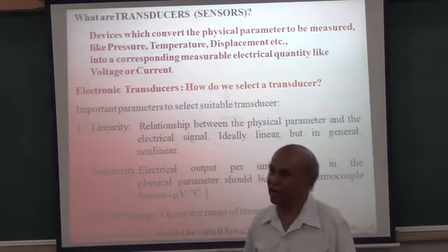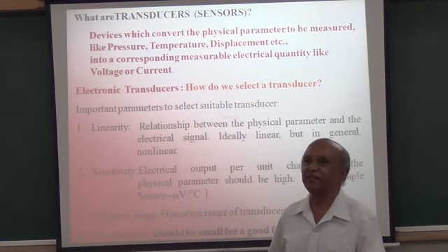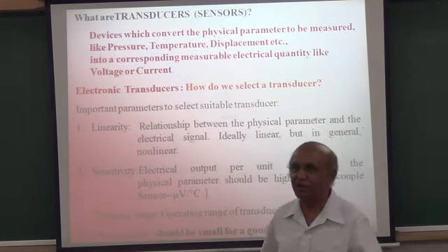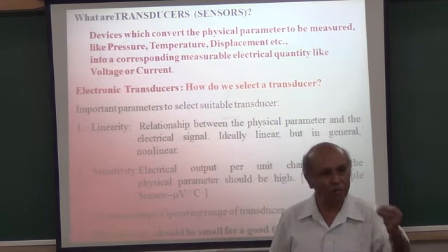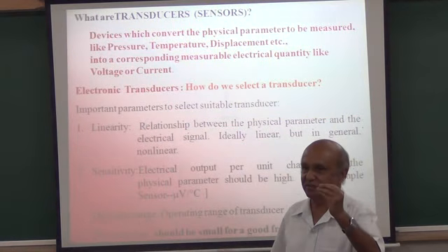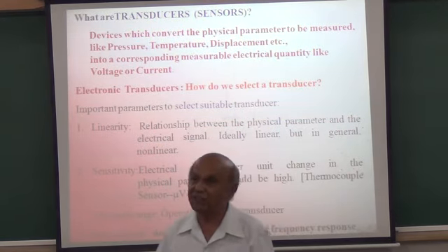What we use there is the property that the resistance of platinum behaves linearly with temperature. Therefore, if I measure resistance, it is equivalent to measuring temperature because I know the slope. But to measure resistance, importantly, you must pass a current. You require an external power source to measure the resistance.